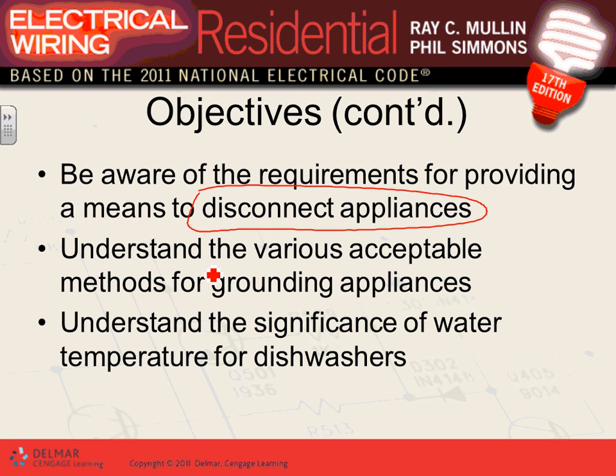Grounding. All appliances must be grounded. So what we do is we provide an equipment grounding conductor. We tie it to the metallic frame of the appliances, with some exception for double insulated appliances, if any.